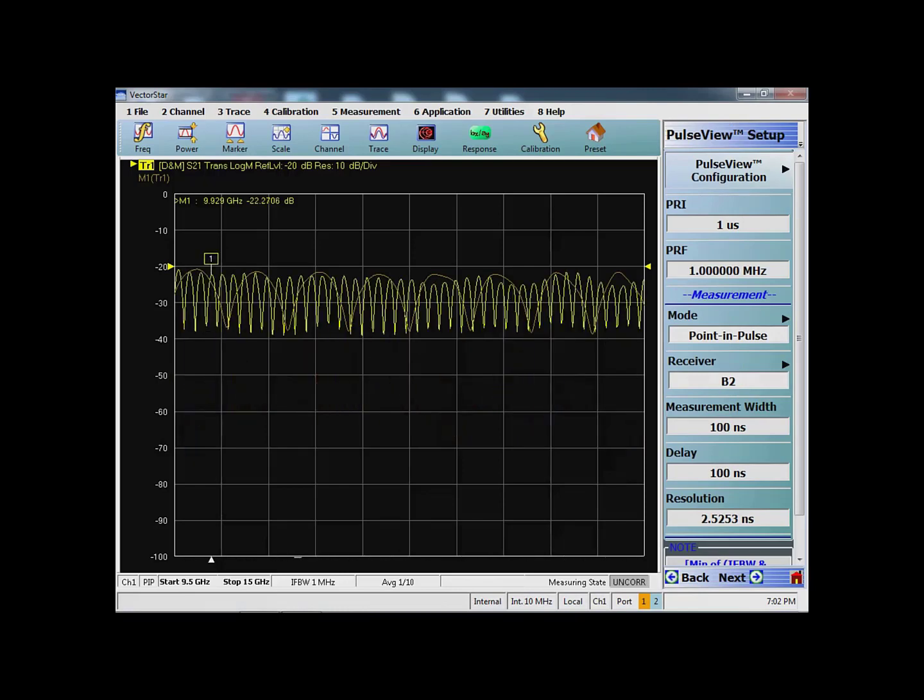Now it so happens that for a lot of customers, they are not satisfied with such a small frequency span. Now we have something called as a continuous profiling as well, in which the entire sweep for the entire duty and for the entire frequency ranges basically happens in one acquisition.